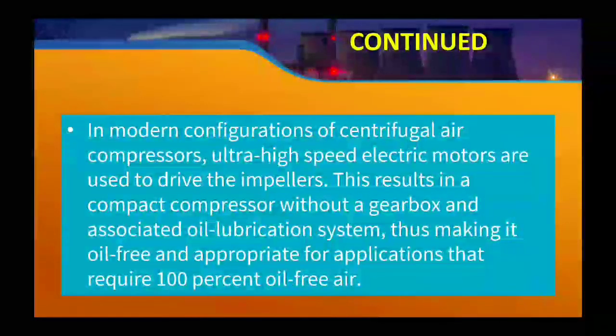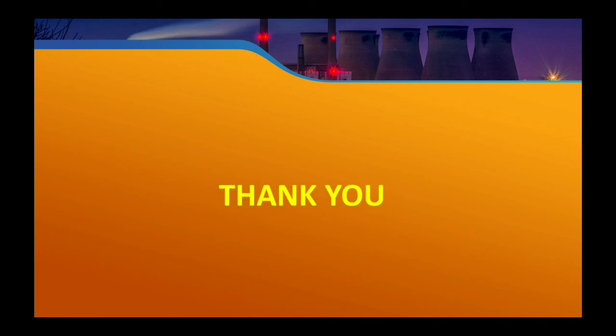In modern configurations, centrifugal air compressors use ultra high-speed electrical motors to drive the impellers instead of gears. When a high-speed electric motor is coupled directly with the impeller, there is no need for a gearbox to increase the impeller speed. With no gearbox, no oil lubrication system is required, making maintenance costs low. This makes the compressor oil-free and appropriate for applications that require 100% oil-free air. That's all for today, thank you.